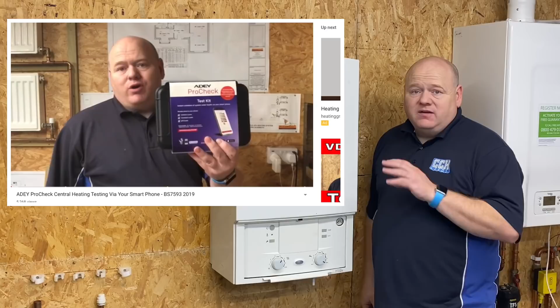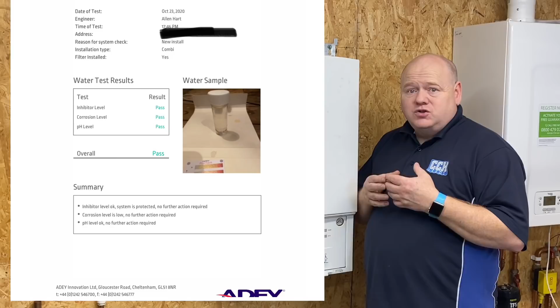I think it's amazing, the customer's reaction when you take a water sample in front of them from the system, so they can see you're not trying to fiddle it. You take pictures, you dip it, show it all in front of them, and they get the results and have proof going forward. So there's no boiler manufacturers getting out of warranties later on, because you can prove it was installed correctly. Each year you can also do that test again.